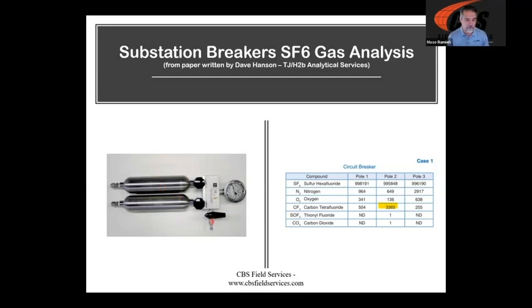Recently, we've seen some 10-year manufacturer specifications where at one time the manufacturer would encourage you to take the gas out of the breaker, take the breaker apart, inspect internal components, and then go through the process of putting it back together. And we've seen some manufacturers recently, particularly southern states on their circuit switchers, has basically removed that requirement. They don't really want anybody cracking their breakers open in the field to do internal inspections. Well, one, I think that speaks to the fact they got plenty of evidence that they're not seeing a lot of degradation on the internals. But two, we're losing out on some valuable information by not doing that inspection.